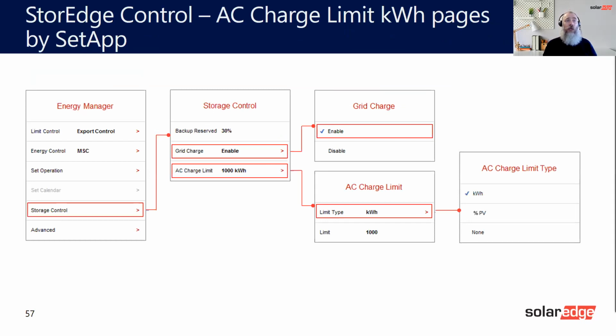The storage control also allows you to set the limit of how much reserve you want in your battery. We recommend the most that you reduce it to is about 11%. You can go down to 9%, but 11% is pretty much it. Then you need to tell it to charge from the grid. So if you run your battery down, your battery won't go to 0%. It will go to 6%, and then it will charge again up to 9%, then reduce to 6% and upgrade to 9% should there be an issue, waiting for either AC charge or for PV excess to charge it. You can also set the limit of discharge and things like that. So it's pretty flexible.